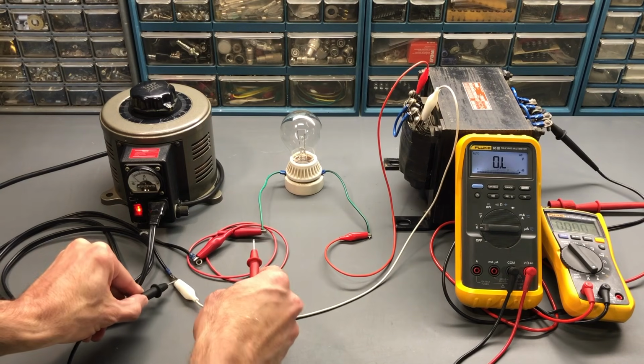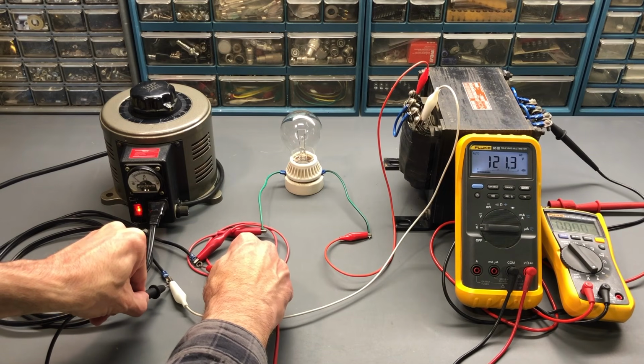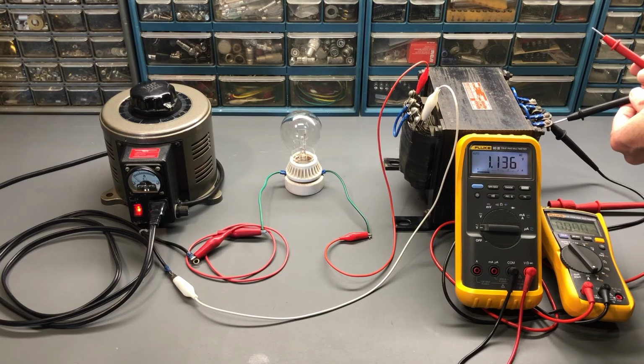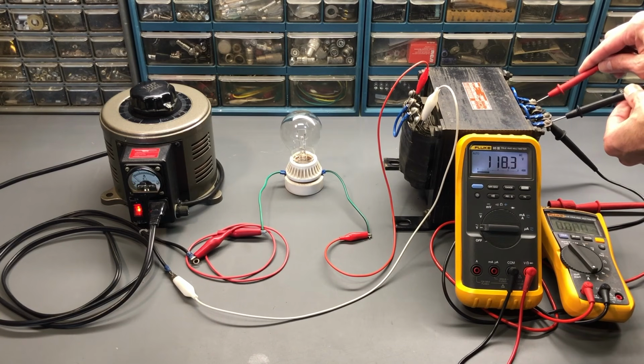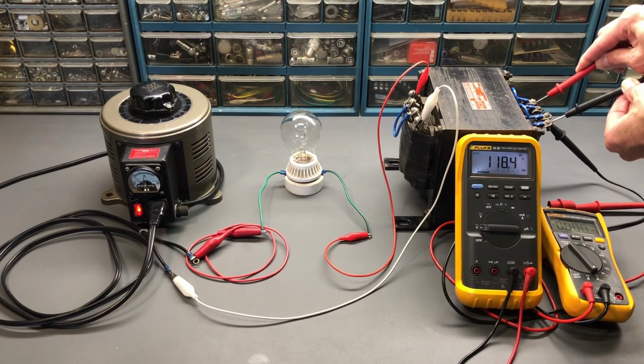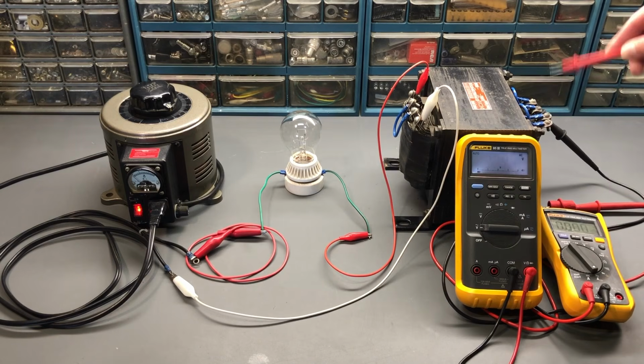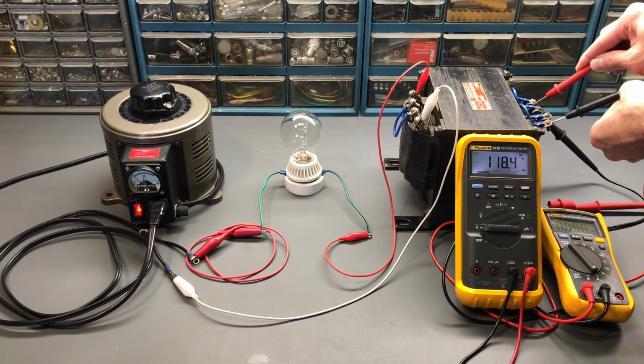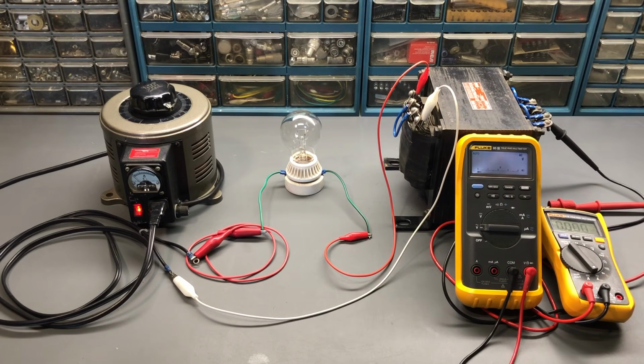Okay, I now have the 100 watt bulb reinstalled. So we'll go back to the Variac. You can see 121.4. That's the voltage coming out of the Variac. And again, I'll go around to the other side of the camera here and take a look at the output. You can see 118. So definitely a higher voltage with the higher wattage bulb. Again, no load on the secondary over here, but there is some loss across that bulb. You can see 118.4, and we have 120, 121 going into the isolation transformer.